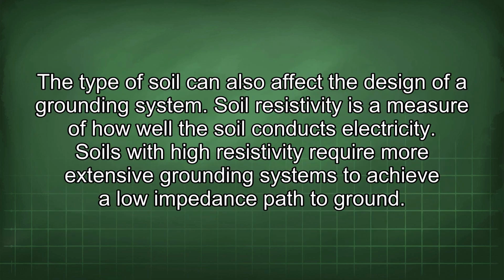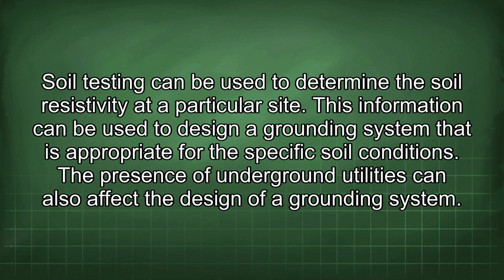The type of soil can also affect the design of a grounding system. Soil resistivity is a measure of how well the soil conducts electricity. Soils with high resistivity require more extensive grounding systems to achieve a low impedance path to ground. Soil testing can be used to determine the soil resistivity at a particular site. This information can be used to design a grounding system that is appropriate for the specific soil conditions.